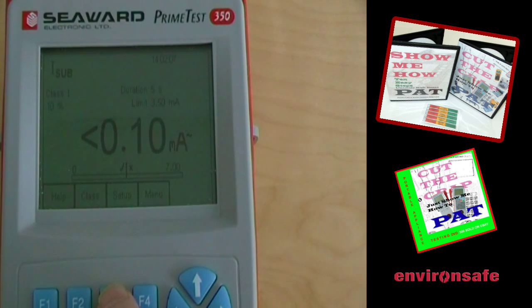F3 allows you to set up the duration of the test as before, from 2 seconds to 30 seconds, and the PF limit from 2.5 to 7. Just scroll up and down using the arrow keys here and the left arrow key to exit this, and we will press escape.